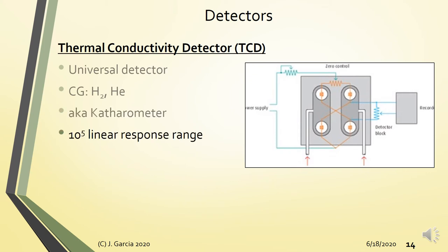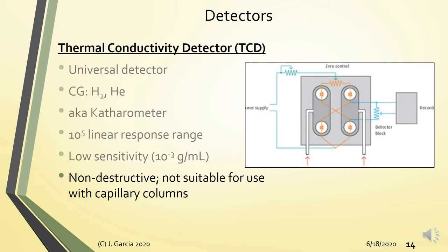Universal detectors like TCD have the lowest sensitivity among GC detectors — around 10⁻³ grams per mL. However, TCD is non-destructive, so if you need to collect eluted components, you can use TCD. It is not recommended for capillary columns and is normally used with packed columns.